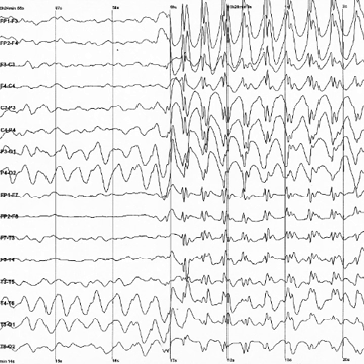Referential montage: each channel represents the difference between a certain electrode and a designated reference electrode. There is no standard position for this reference. It is, however, at a different position than the recording electrodes. Midline positions are often used because they do not amplify the signal in one hemisphere versus the other, such as Cz, Fz, Pz, etc. as online reference.